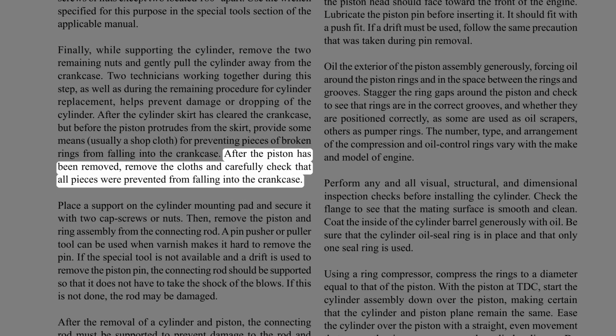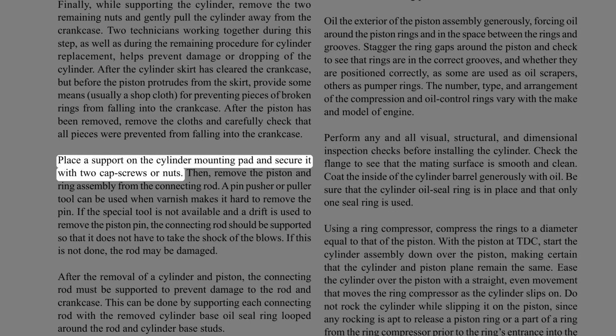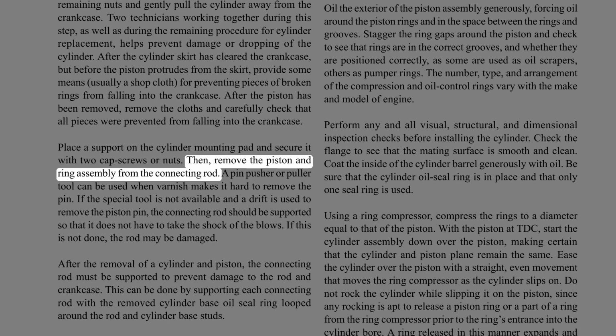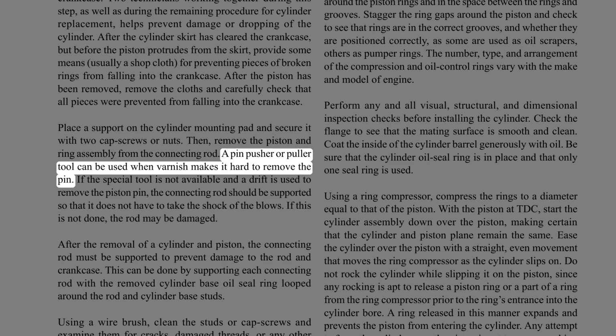After the piston has been removed, remove the cloths and carefully check that all pieces were prevented from falling into the crankcase. Place a support on the cylinder mounting pad and secure it with two cap screws or nuts. Then, remove the piston and ring assembly from the connecting rod. A pin pusher or puller tool can be used when varnish makes it hard to remove the pin.